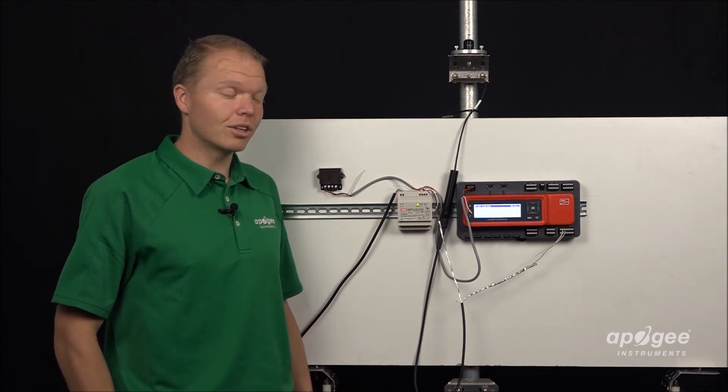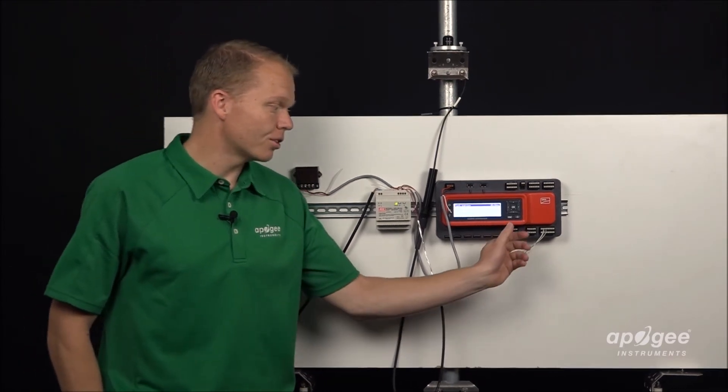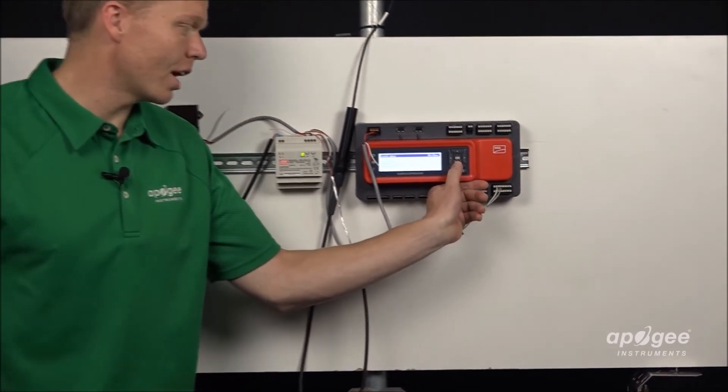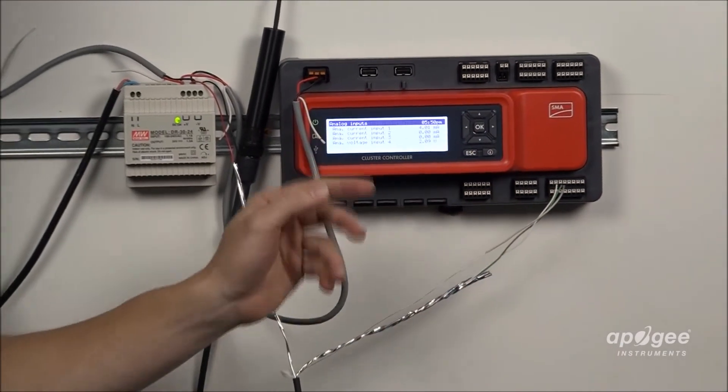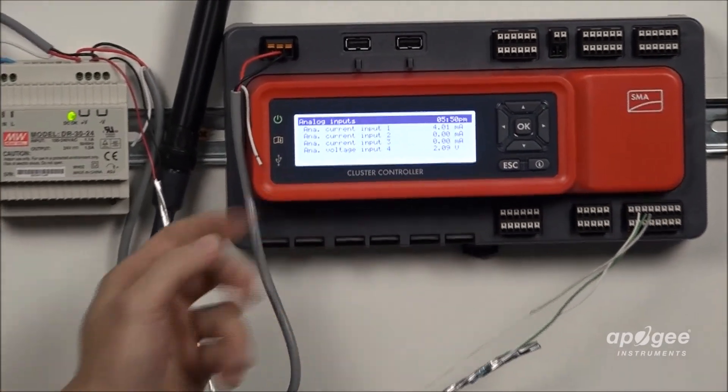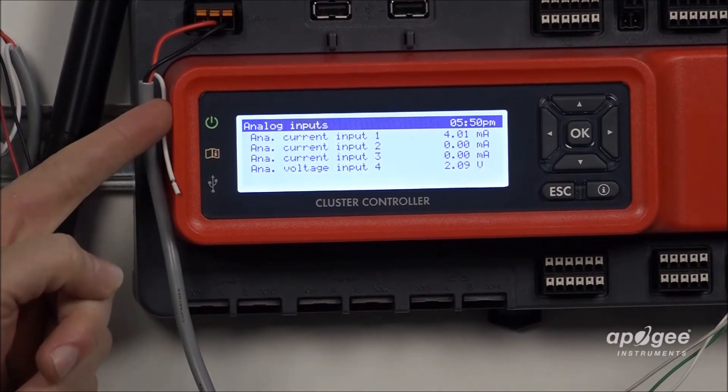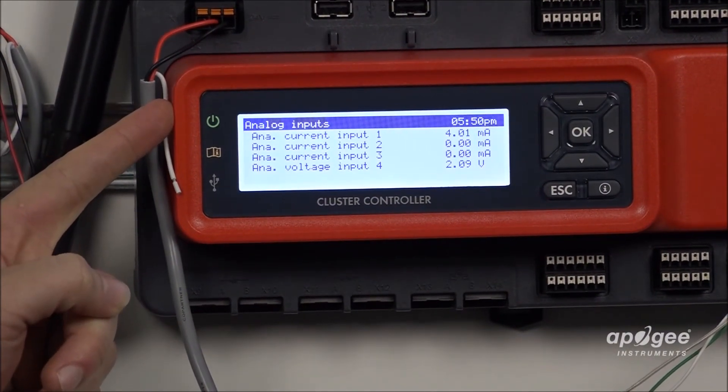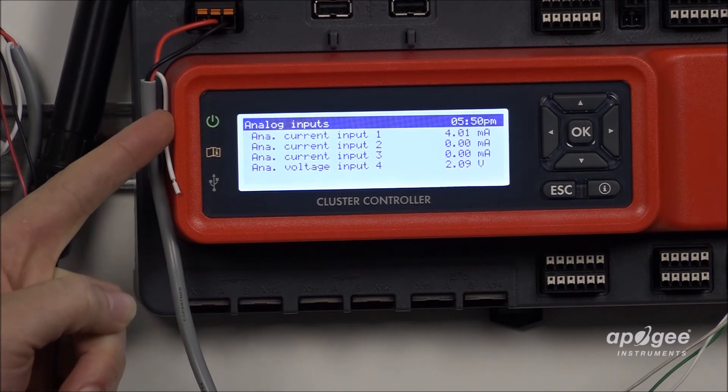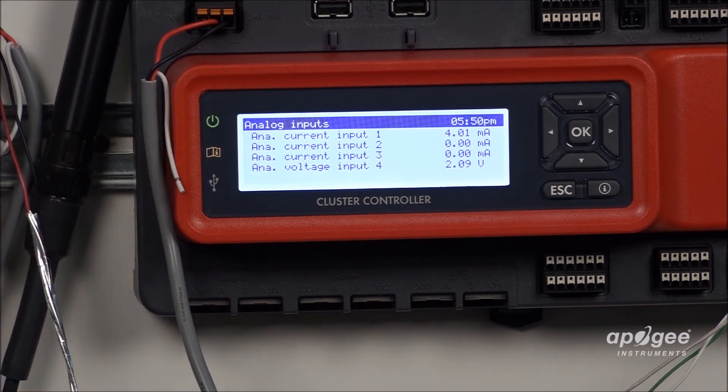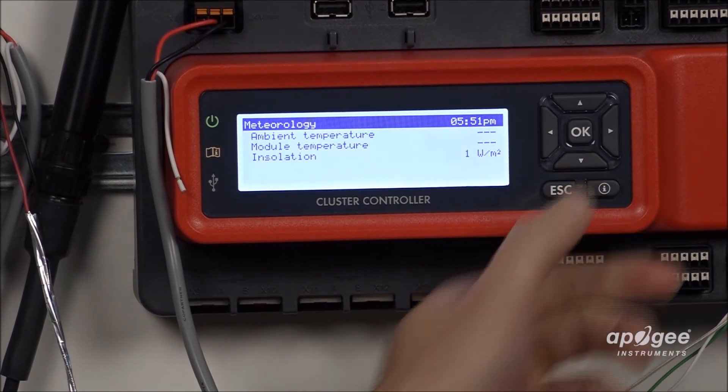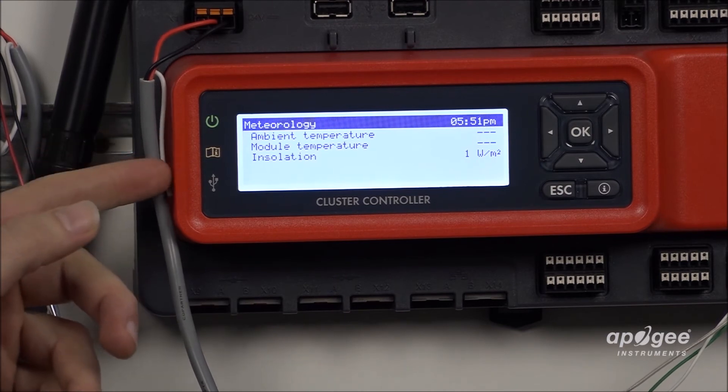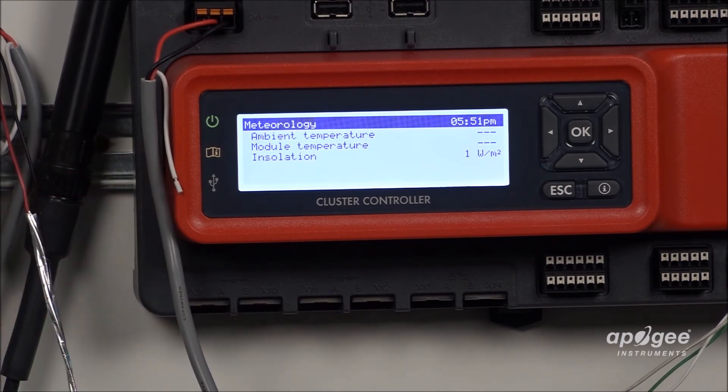The other way that you can look at this is on the controller itself. If you scroll down a number of times you get to analog inputs. Analog current input number one on the top there is showing us the data reading from the sensor and in our example here it's reading 4.01 milliamp which is correct for our studio. There is very little light and if we hit down two more times we can see the insolation converting that to 1 watts per meter square.